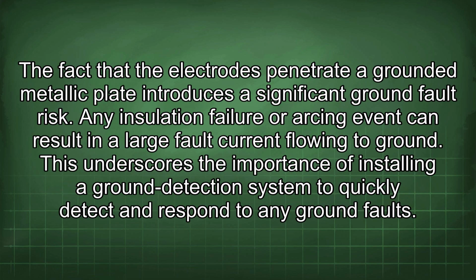The fact that the electrodes penetrate a grounded metallic plate introduces a significant ground fault risk. Any insulation failure or arcing event can result in a large fault current flowing to ground. This underscores the importance of installing a ground detection system to quickly detect and respond to any ground faults.